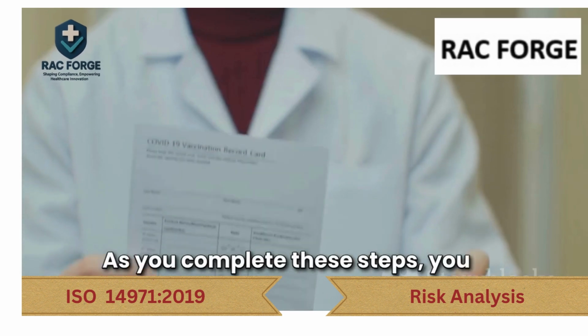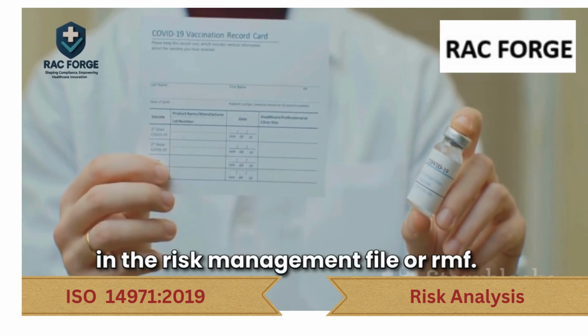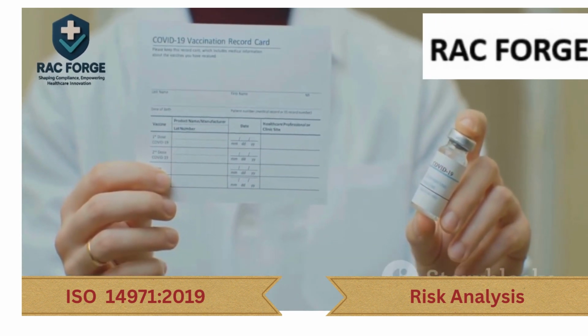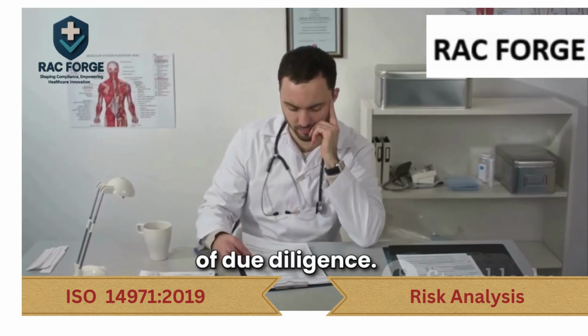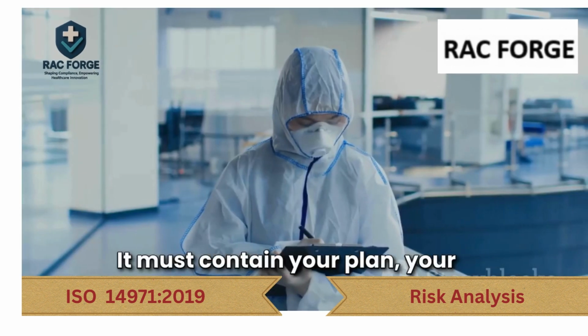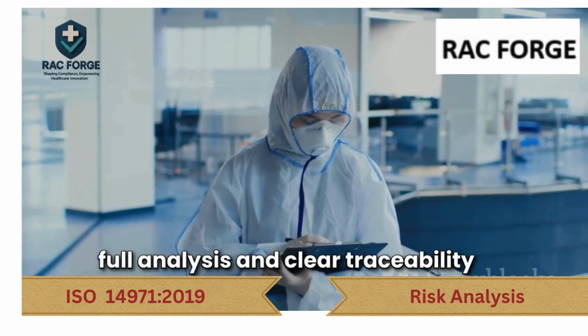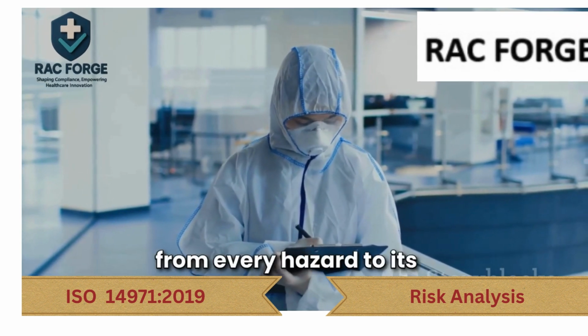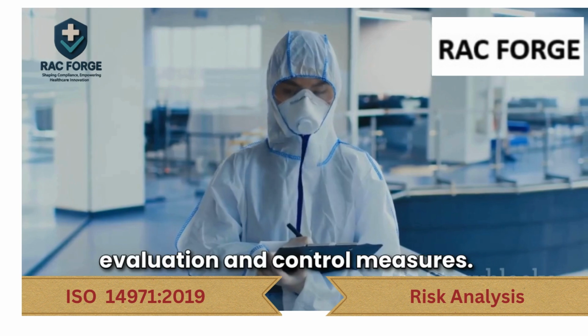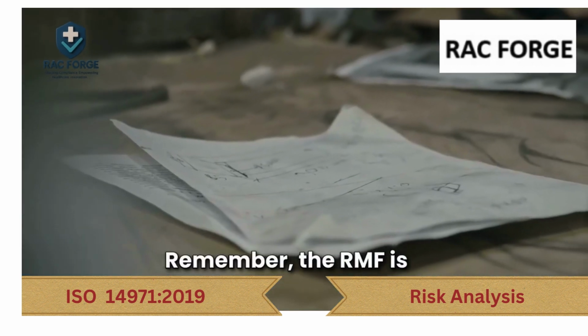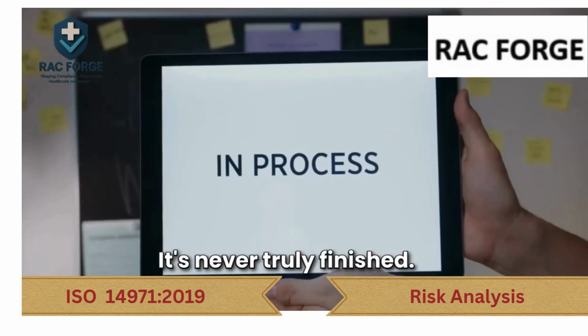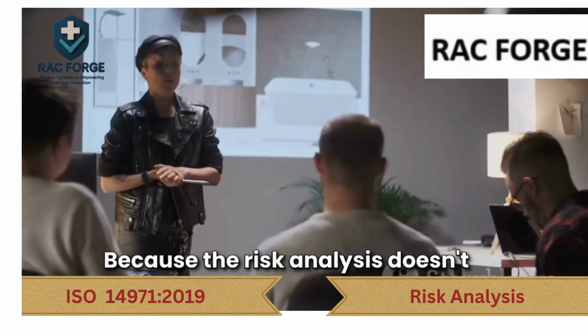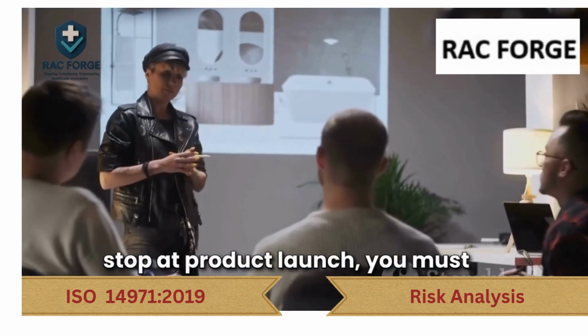As you complete these steps, you must document everything in the Risk Management File, or RMF. This file is your proof of due diligence. It must contain your plan, your full analysis and clear traceability from every hazard to its evaluation and control measures. Remember, the RMF is a living document. It's never truly finished, because the risk analysis doesn't stop at product launch.